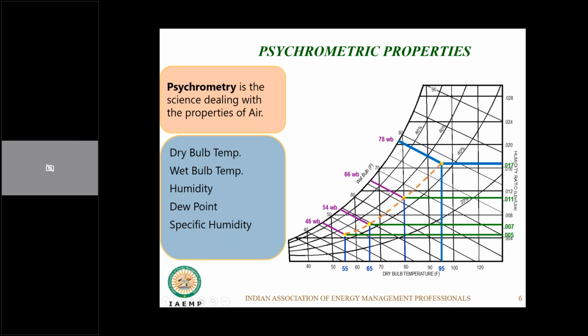Let's say for a particular application, we have measured a dry bulb of 80 degrees Fahrenheit and a wet bulb of 66. The intersection is here. From here, we can establish all the other properties of the air from the psychrometric chart. So here we can say the humidity at this point is 50%. It is between 40 and 60, so we say humidity is 50%. We'll talk a little more on humidity later. I'll come again over there.